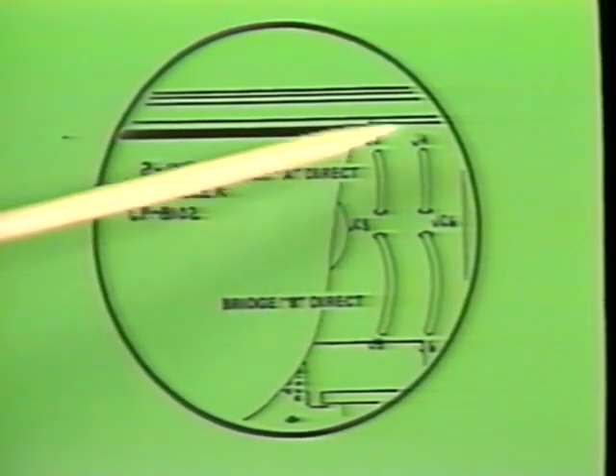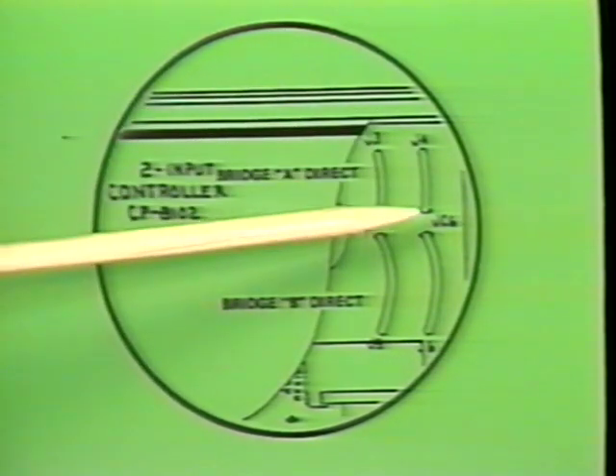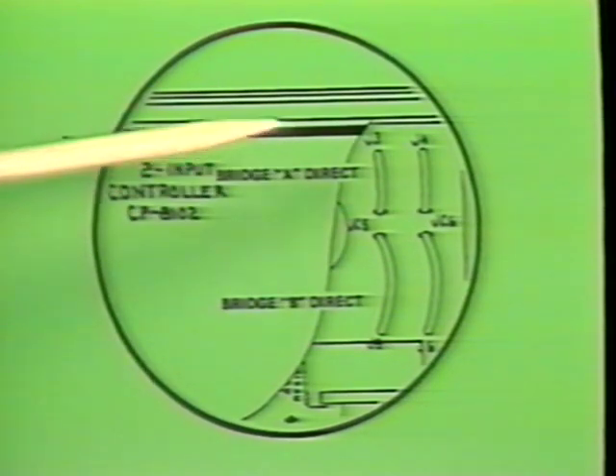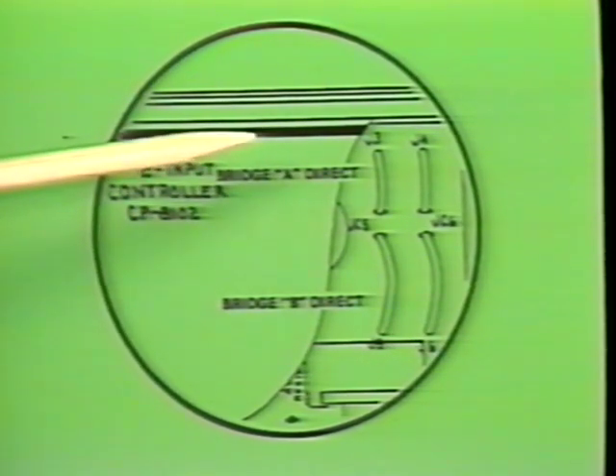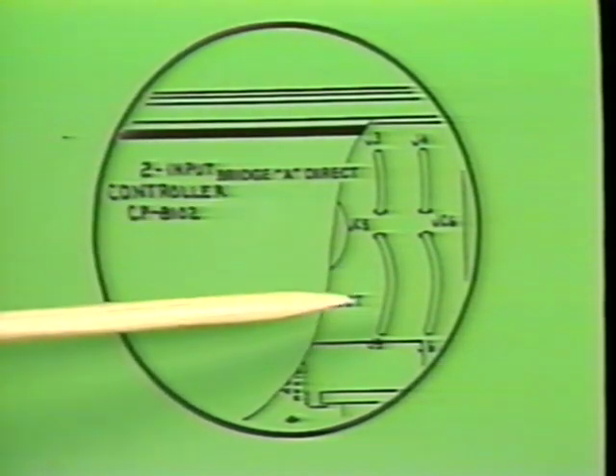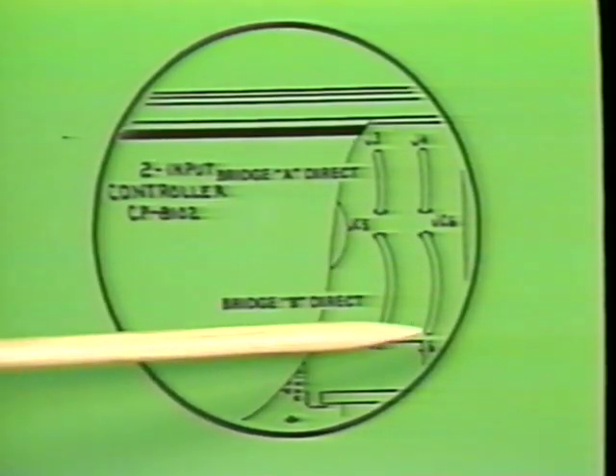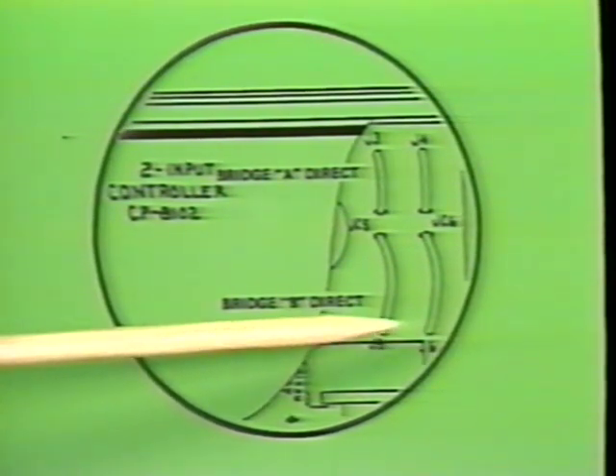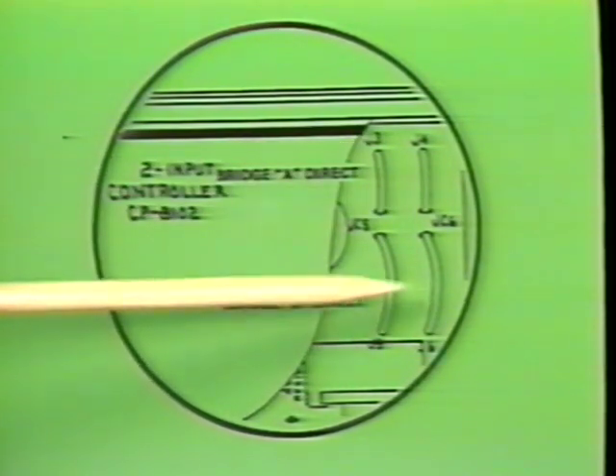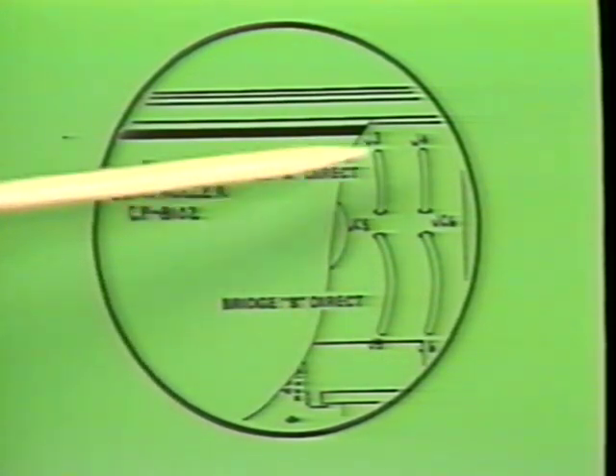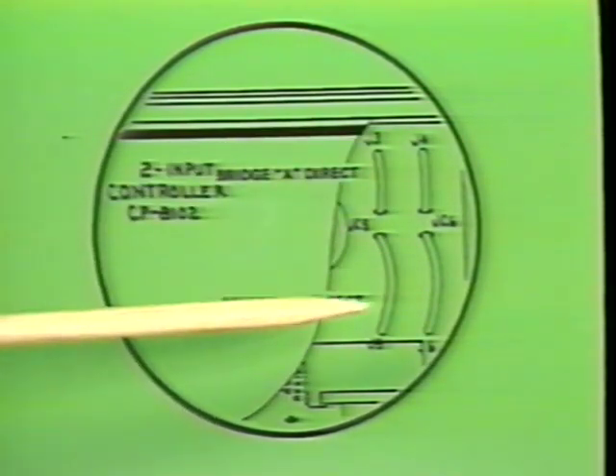To review the action jumpers, let's look at this chart. Note that J3 and J4, the upper jumper pair, is parallel. That means that bridge A and the controller are direct acting. Bridge B also is parallel. However, the important point to note here is when the B jumpers are the same as the A jumpers, the reset effect is reverse.